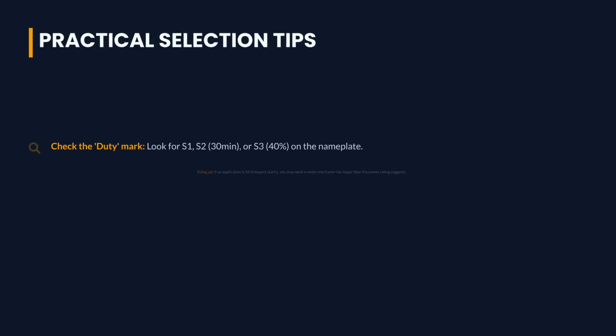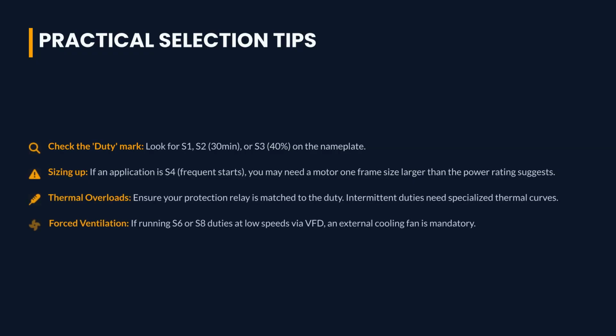For practical selection, always check the duty mark on the motor nameplate. For intensive duties like S4, you may need a larger motor frame size. Ensure your thermal overload protection matches the duty cycle.